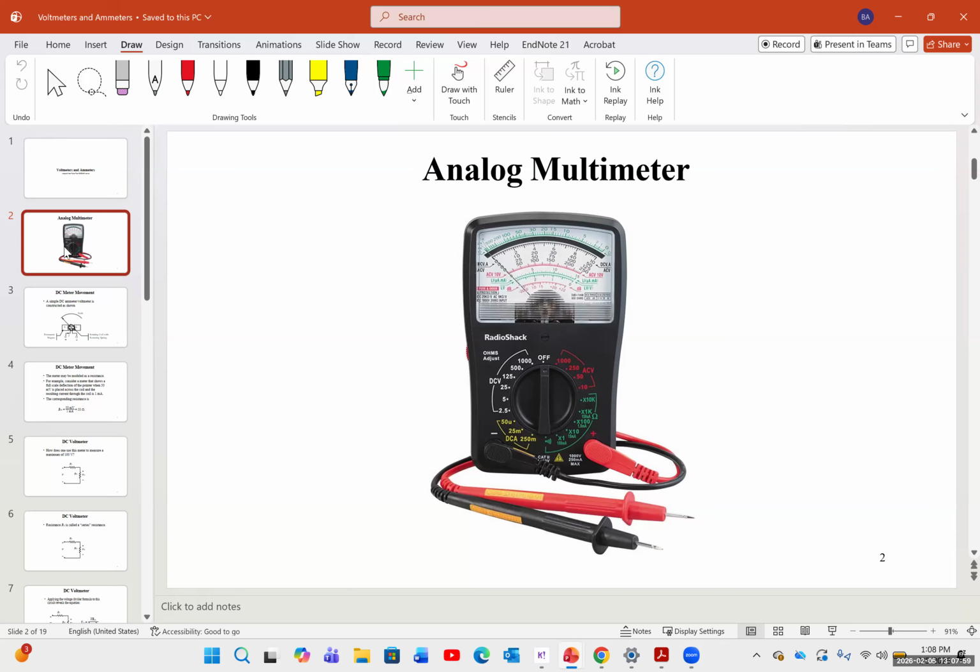And because they have mechanical elements such as a spring, if you put it on a shock, any sudden movement would cause an error and deflect that spring and cause a permanent error in the system. Also, it's prone to error when you put it in a magnetic field or on a high voltage. If you put it in a very high voltage, the internal coil would be destroyed.